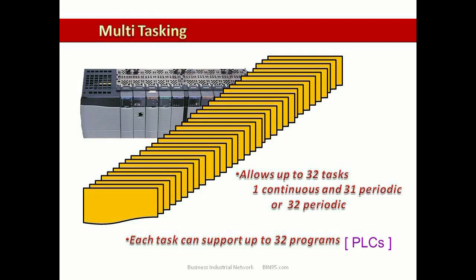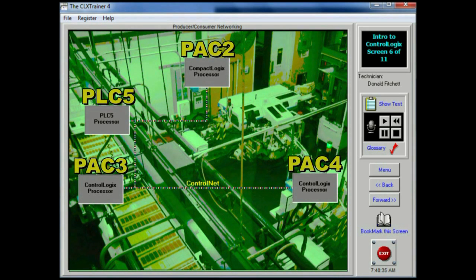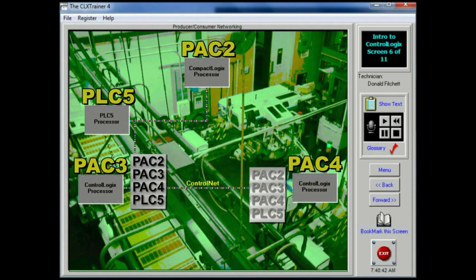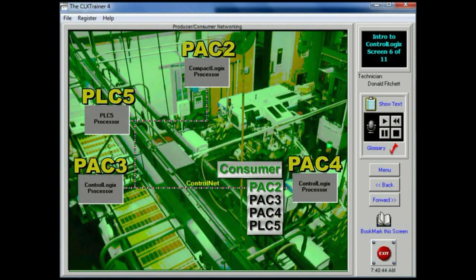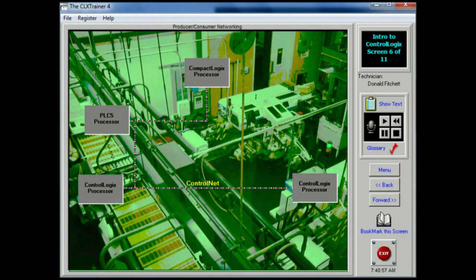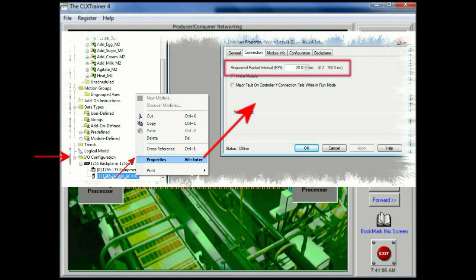Each one of these programs can have their own data and logic. The producer-consumer network model is used by the ControlLogix system. In this type of network, the producer places a connection ID at the beginning of the data packet. The packet or message is then multicast, and each module screens the ID to determine if it needs the data. If it does, then that module becomes the consumer. This allows one or many modules to listen for and consume data with its specific connection ID while discarding or ignoring all others. Individual modules can produce data without having been polled by a controller first. Data will be multicast based on either a time interval or a change of state.